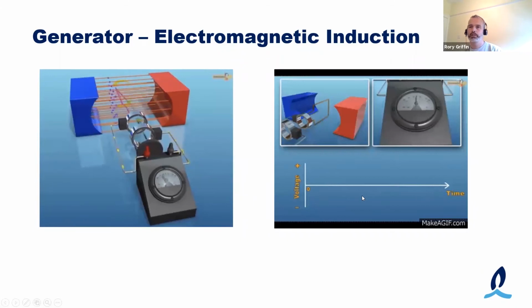A few other bits and things to bear in mind when the unit is synchronizing to the grid. As the machine is running up, you close the circuit breaker, you do a sync close, so the rotation of the shaft is matched with the grid frequency. So ideally you're at 50 Hertz, and the machine's at 3000 RPM. And what happens then is the machine block loads. It doesn't just linearly ramp up 0, 1, 2, 3. You might jump on and straight away you're supplying 20 megawatts.